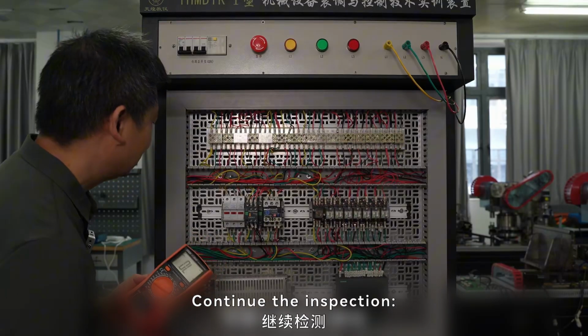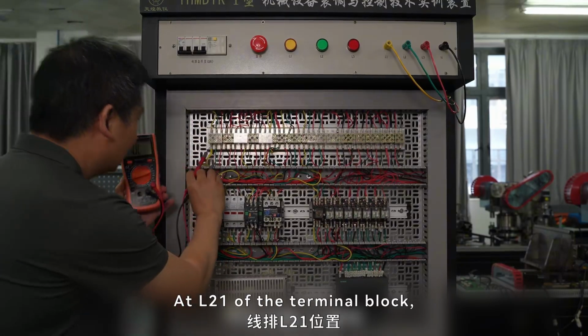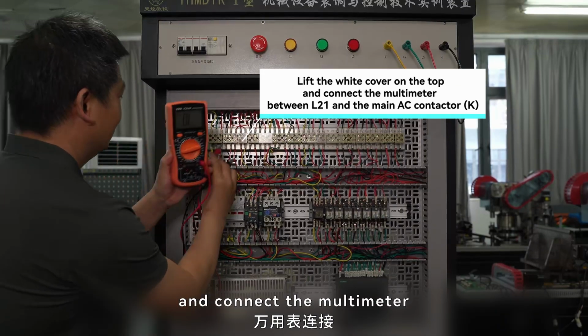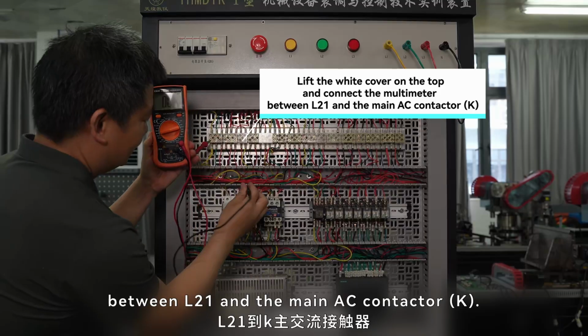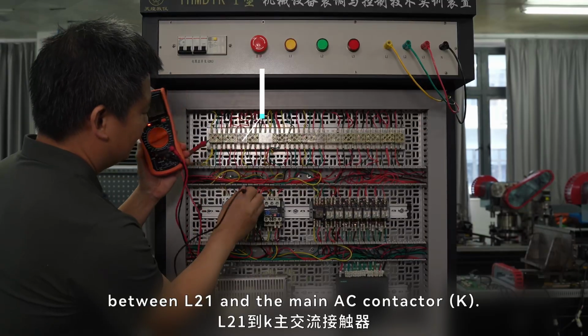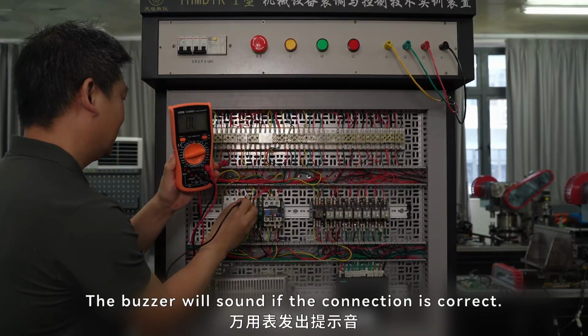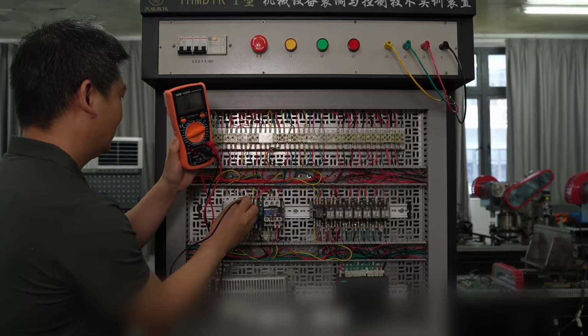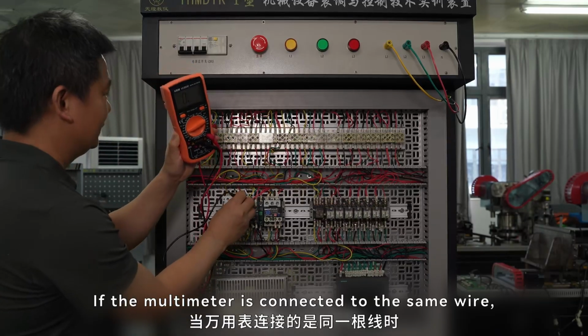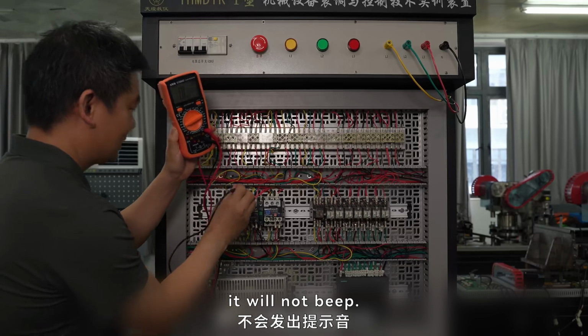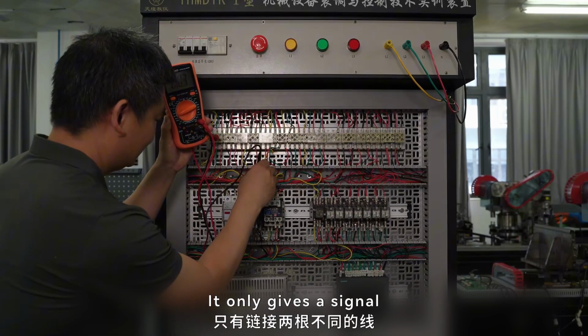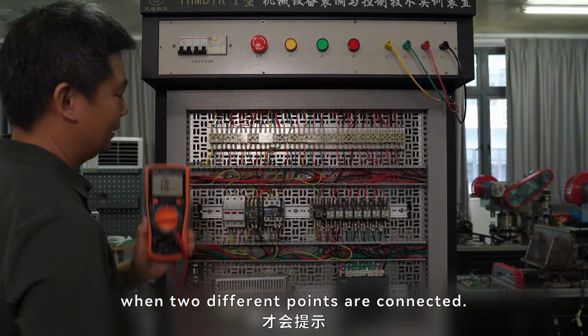Continue the inspection. At L21 of the terminal block, lift the white cover on the top and connect the multimeter between L21 and the main AC contactor K. The buzzer will sound if the connection is correct. If the multimeter is connected to the same wire, it will not beep. It only gives a signal when two different points are connected.